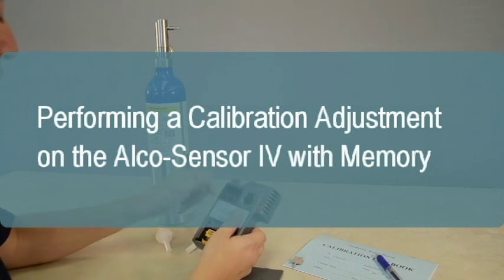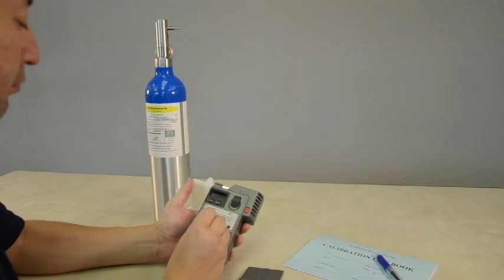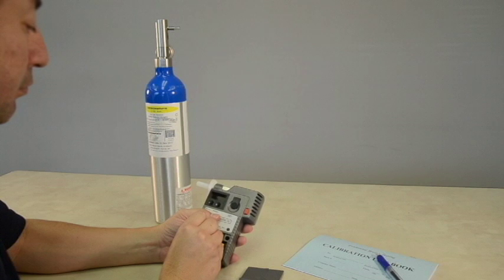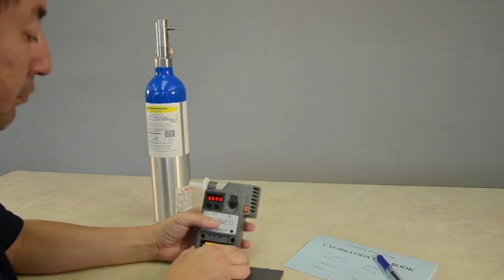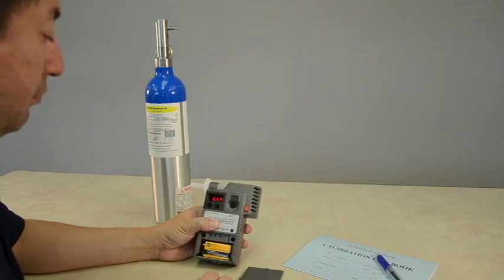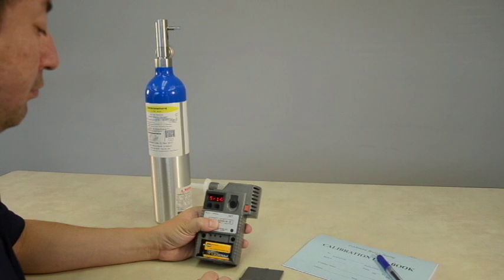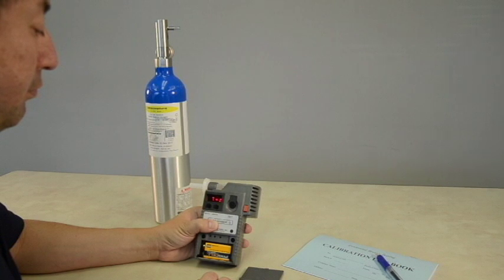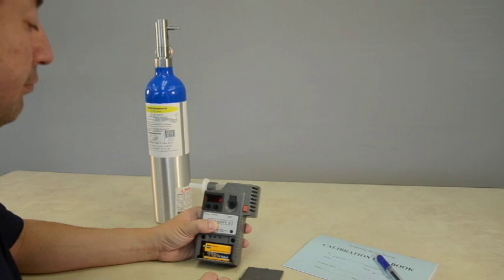AlcoSensor IV instruments typically hold their calibration for months or even years without needing adjustment. Intoximeters does not require that the instruments be periodically calibrated. A calibration adjustment need only be performed if an accuracy check on the instrument has failed. It is important to note if your company performs DOT alcohol screening tests using the AlcoSensor IV with memory, we strongly recommend you refer to the manufacturer's policy on who is authorized to perform calibrations.